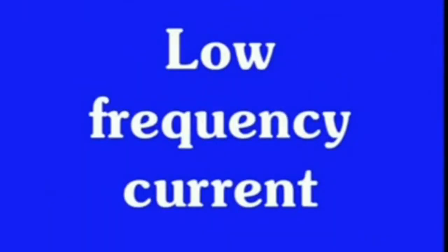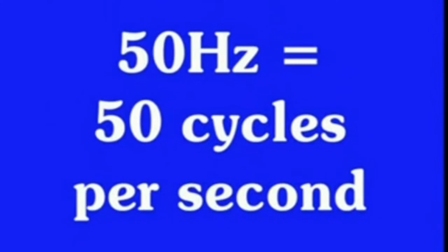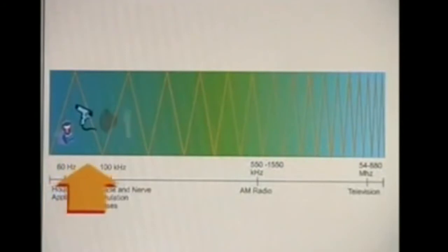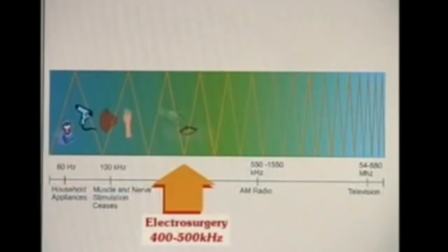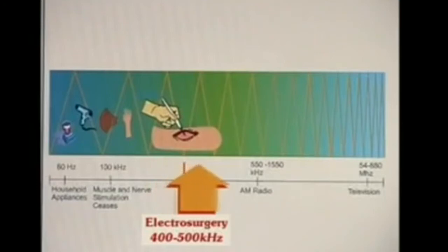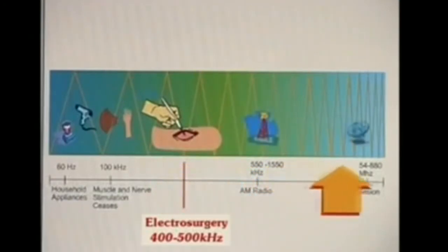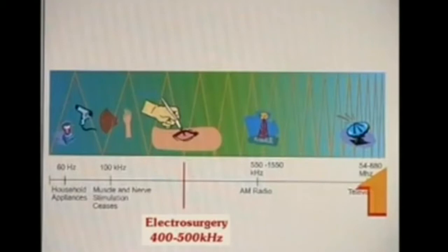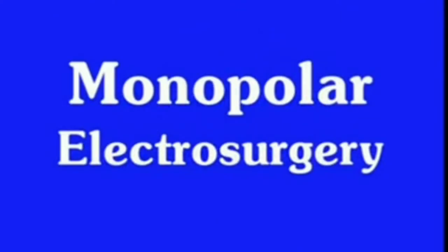Low-frequency current, such as the mains, which alternates 50 times per second or at 50 Hz, leads to neuromuscular stimulation and potential cardiac arrest. Electrosurgical generators deliver a much higher frequency, around 400 to 500 kHz, and it is this that prevents neuromuscular stimulation and allows the current to pass safely through the body. There are two methods of applying electrosurgery: monopolar and bipolar. We will deal firstly with monopolar electrosurgery.